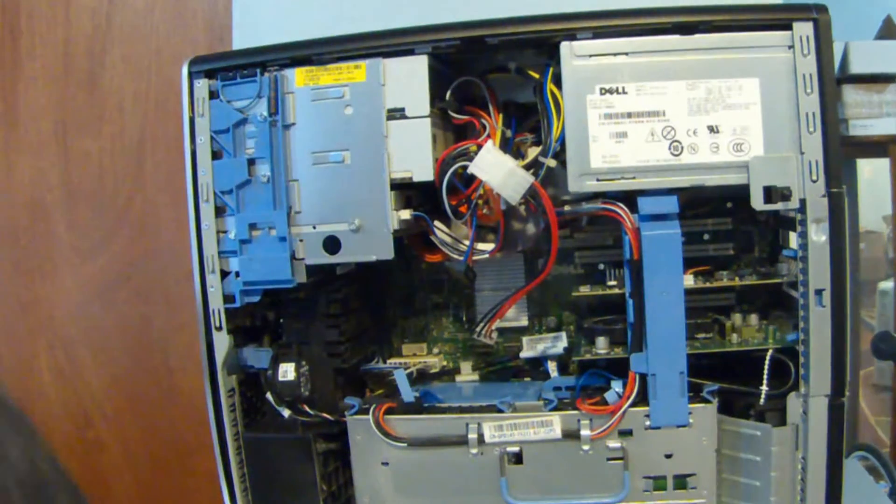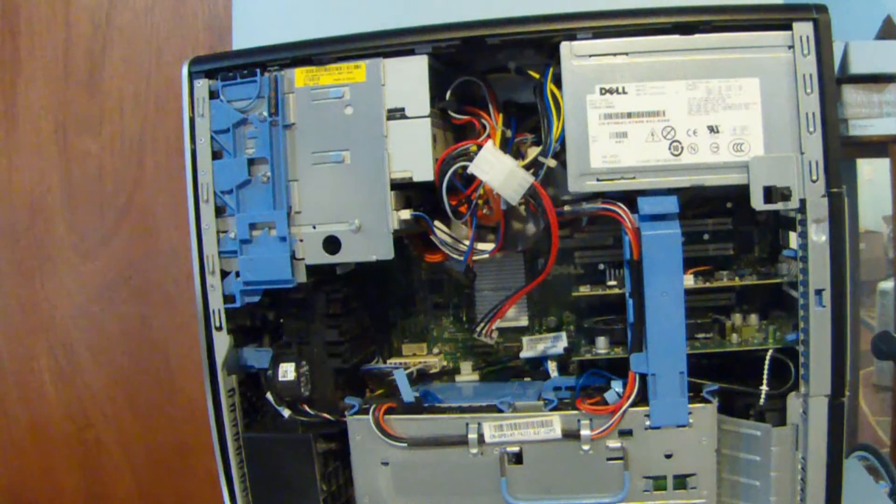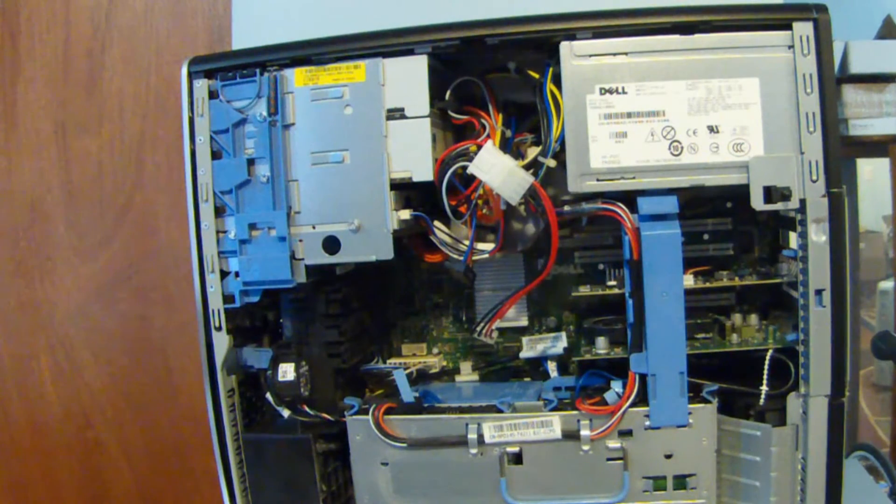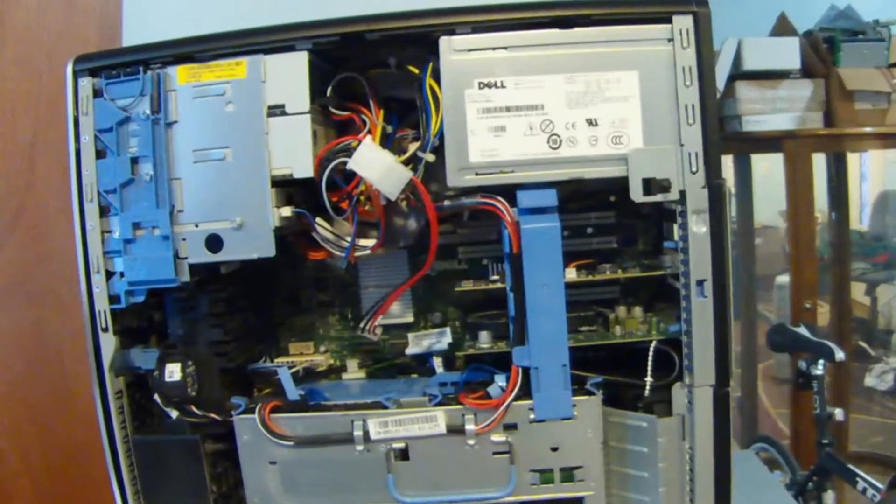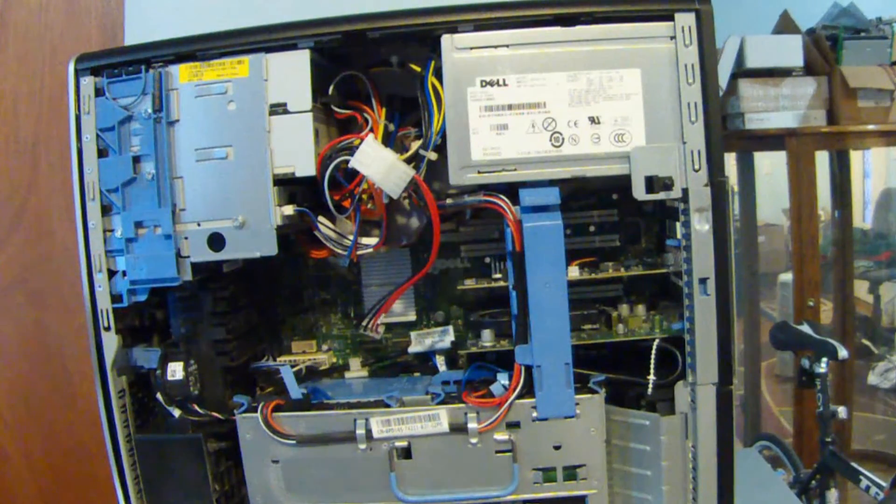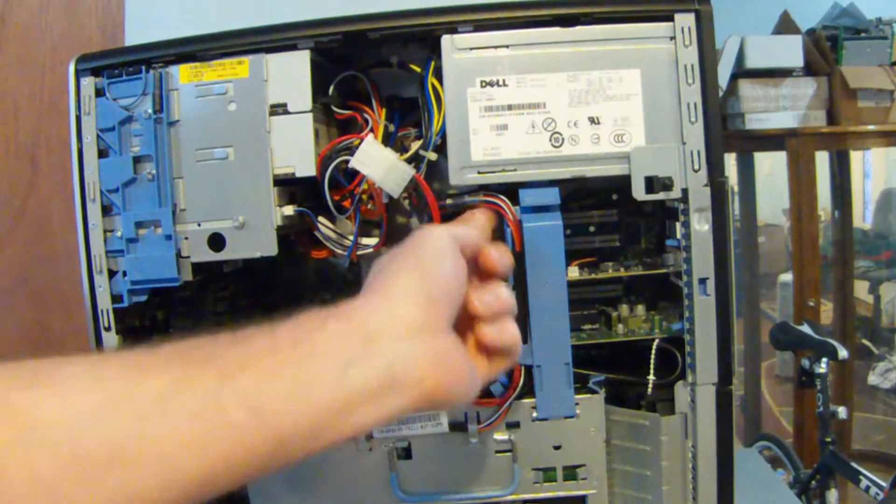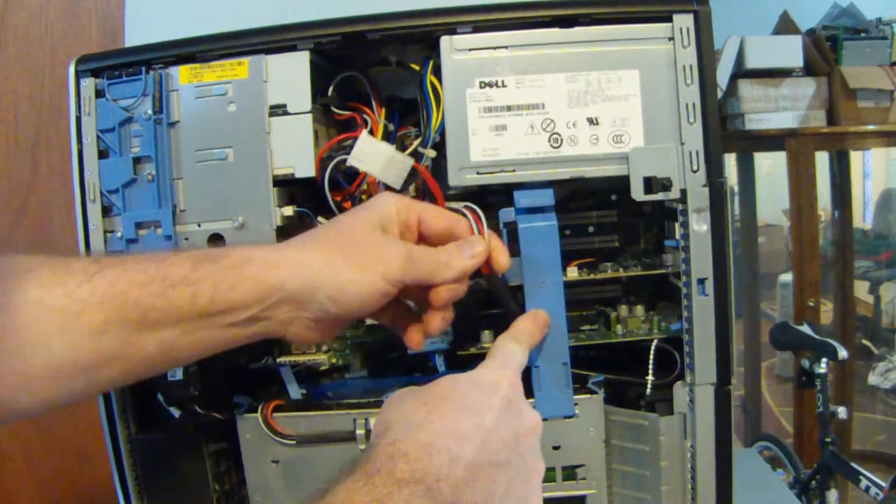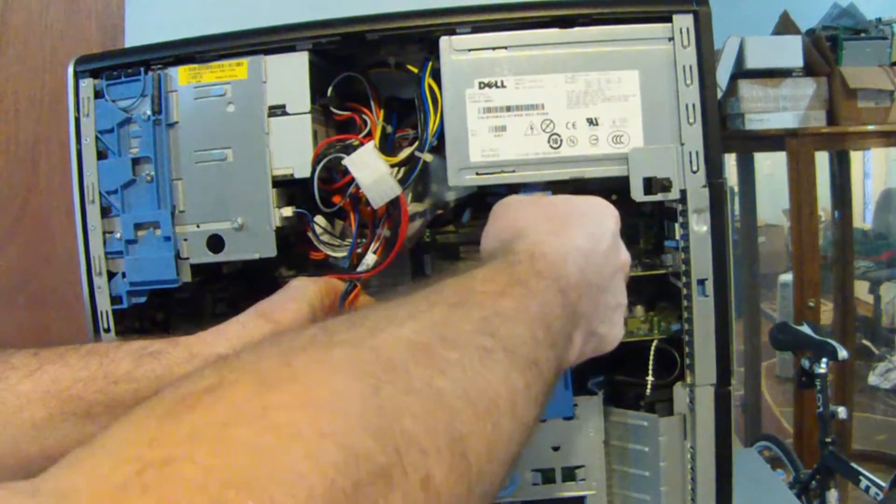Then with the clip on the top, we're going to release the side cover. Next, there's wires in the little blue arm, and we're going to remove these wires from the little blue arm and just push those wires out of the way.